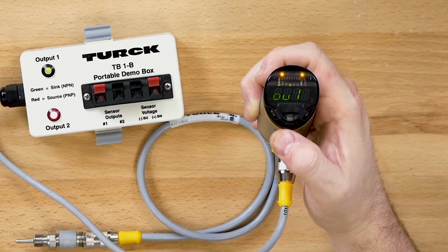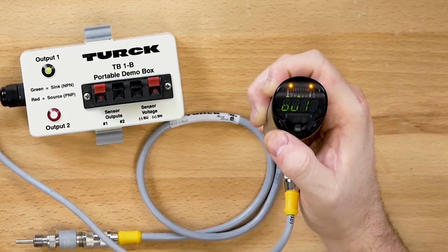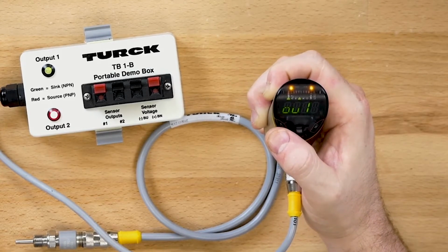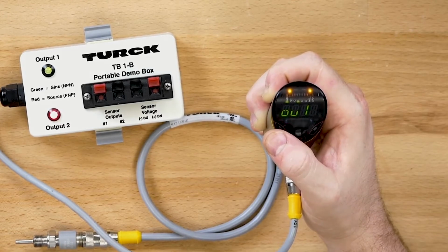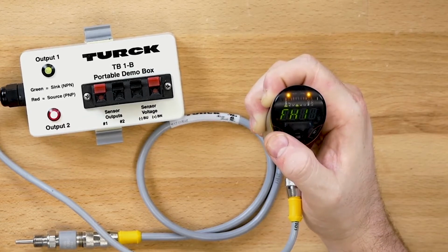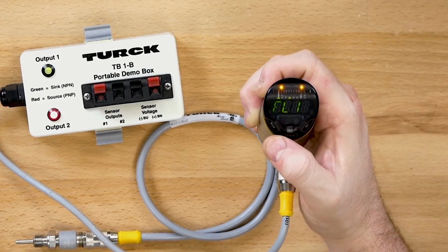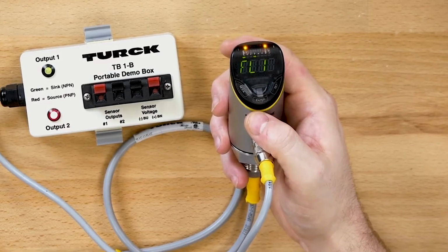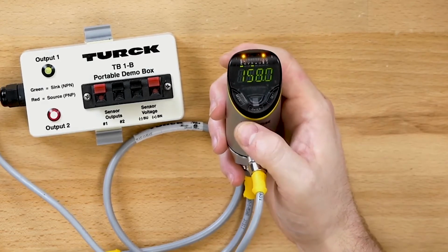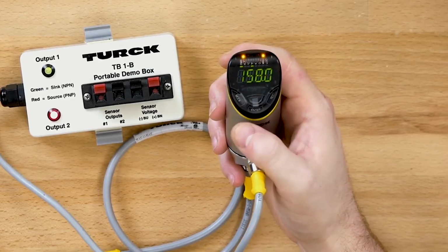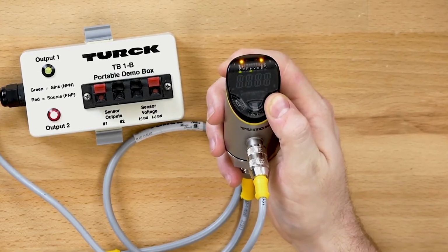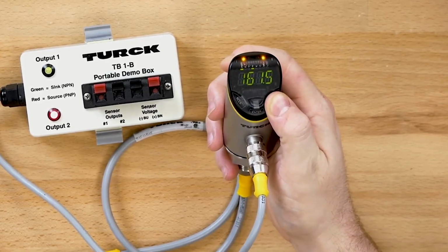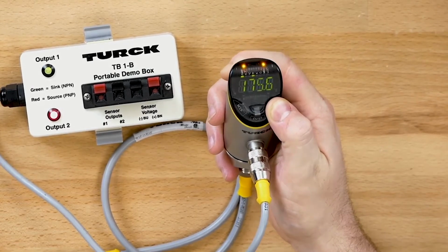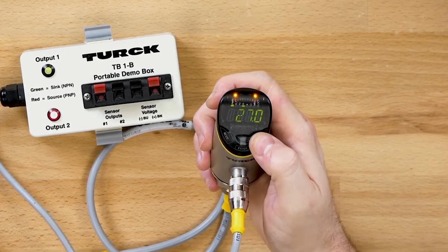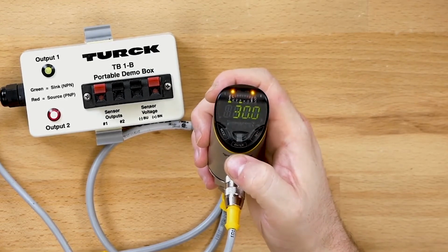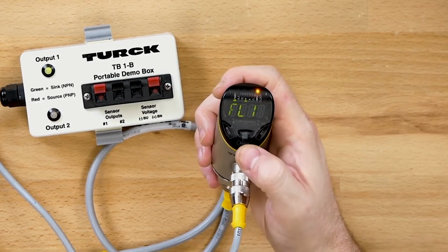With window mode set, let's set up our 30 degree Fahrenheit limit. Remember, we are setting the sensor to have a PNP output on output 1 when the temperature is between 30 and 80 degrees Fahrenheit. Using the Mode and Set buttons to navigate the menu, go to the FL1 menu, which sets the lower window limit. With the FL1 menu displayed, clicking Enter displays the value. Let's change that to our lower limit of 30 degrees Fahrenheit. Holding the Set button for 3 seconds until the display stops blinking allows us to change this parameter. We want to change that to 30 degrees Fahrenheit. Clicking Enter enters the value. The lower limit is now set to 30 degrees Fahrenheit.